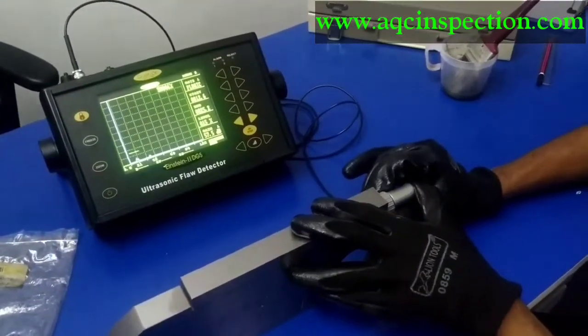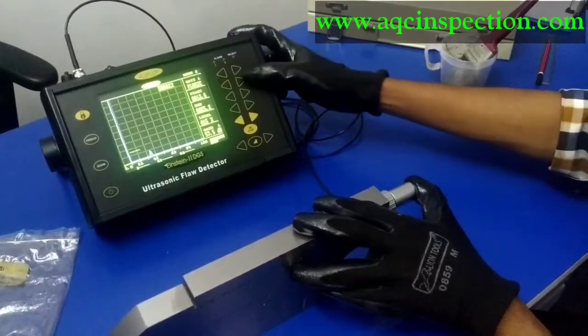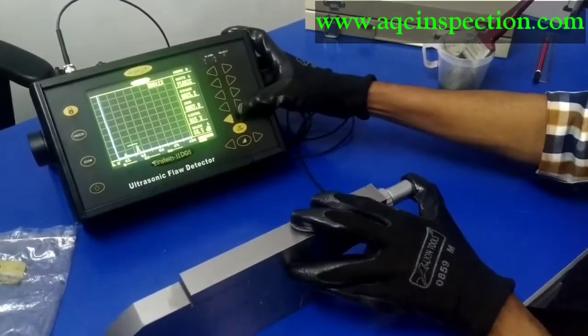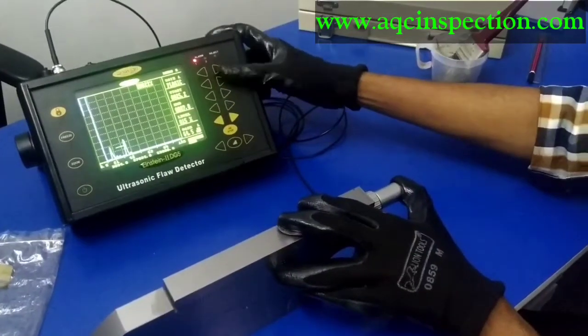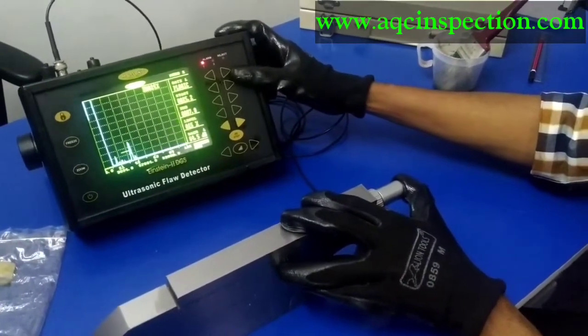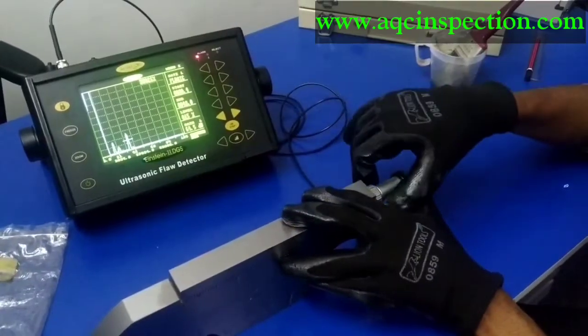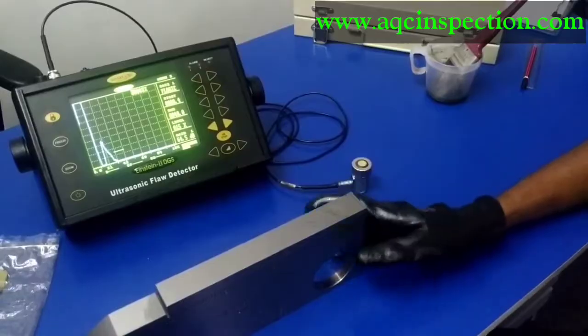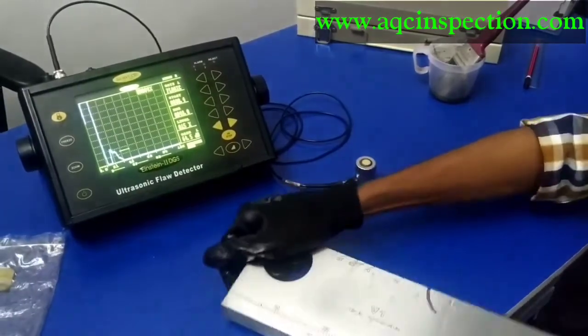Yes, I am getting it. Remove the gate. Also increase the gain value. I am getting 34.8 mm. This is how you set for the sensitivity calibration.